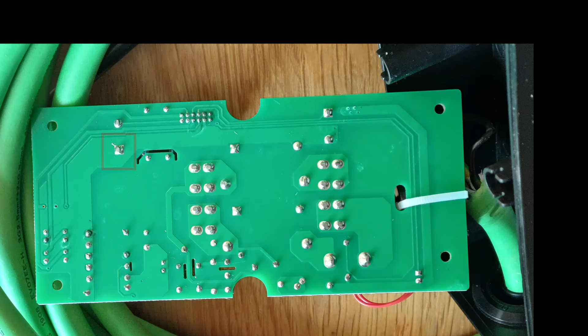There's a weird thing about pen faults. What we learn when we study electrical systems is that the protective earth conductor, officially called the CPC, should always be unbroken. It's there for safety and should always remain intact. It shouldn't go through breakers or switches. It has to remain attached at all times, except in the case of a pen fault. The peculiarity of this fault condition is that we have to go against our instincts. In this fault scenario, it's the CPC itself that carries the risk. It is what could expose us to dangerous voltages.